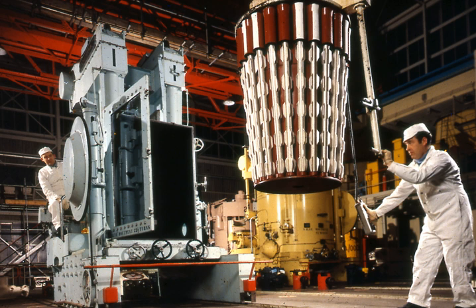Like other plutonium-producing reactors, conserving neutrons is a key element of the design. In Magnox, the neutrons are moderated in large blocks of graphite. The efficiency of graphite as a moderator allows the Magnox to run using natural uranium fuel, in contrast with the more common commercial light-water reactor which requires slightly enriched uranium. Graphite oxidizes readily in air, so the core is cooled with CO2, which is then pumped into a heat exchanger to generate steam to drive conventional steam turbine equipment for power production.